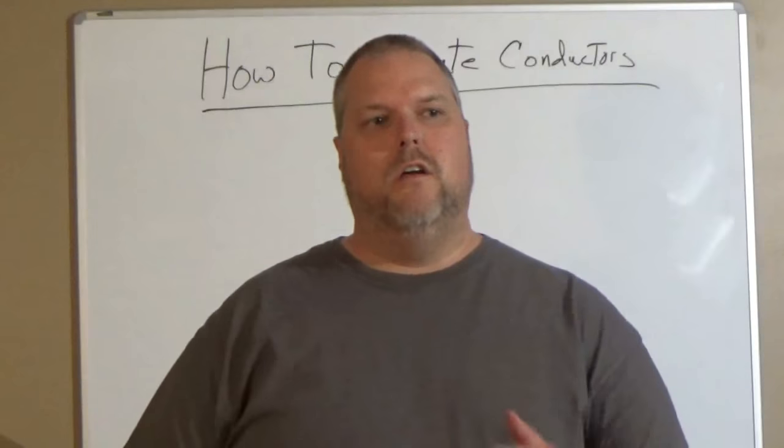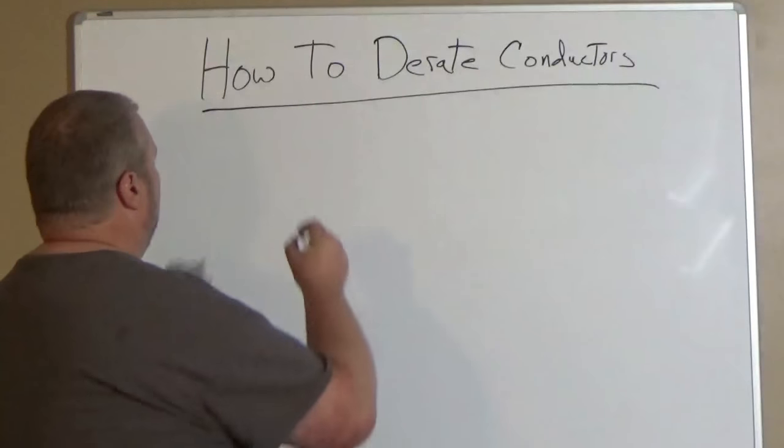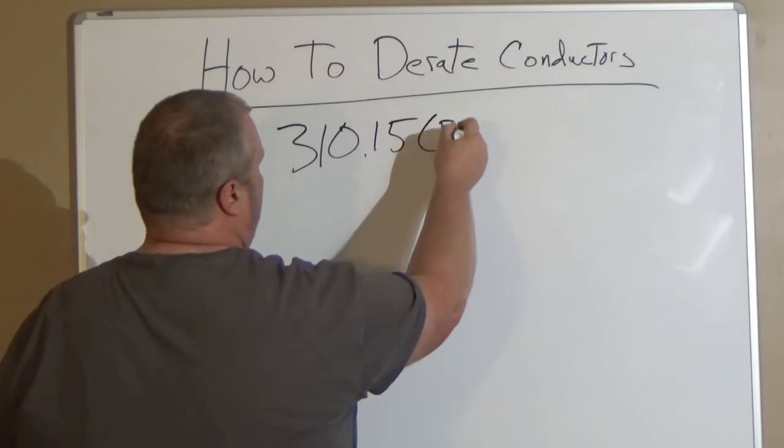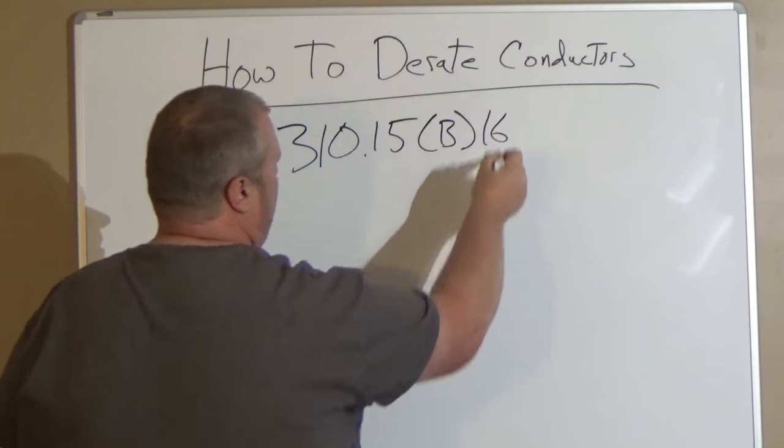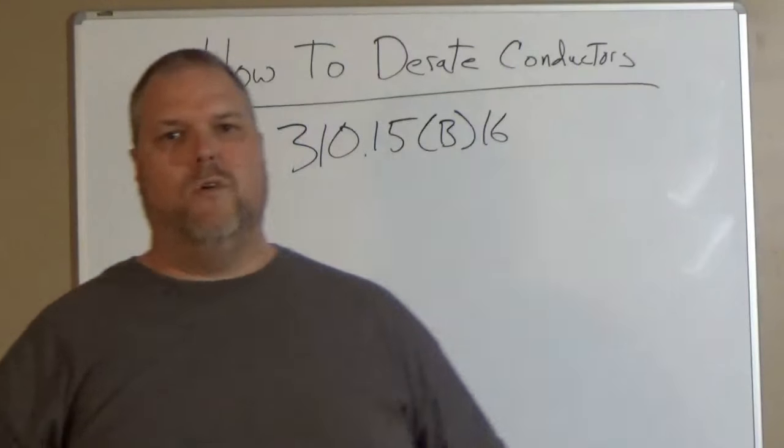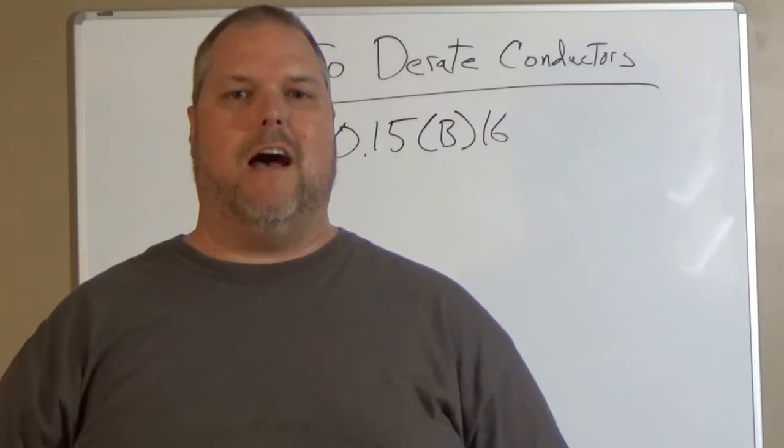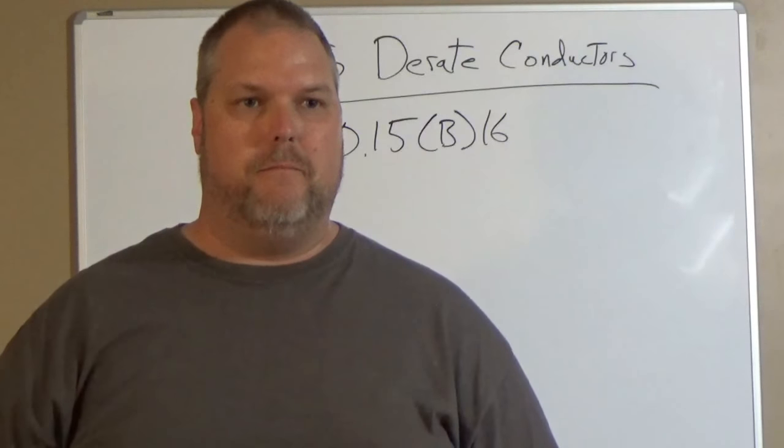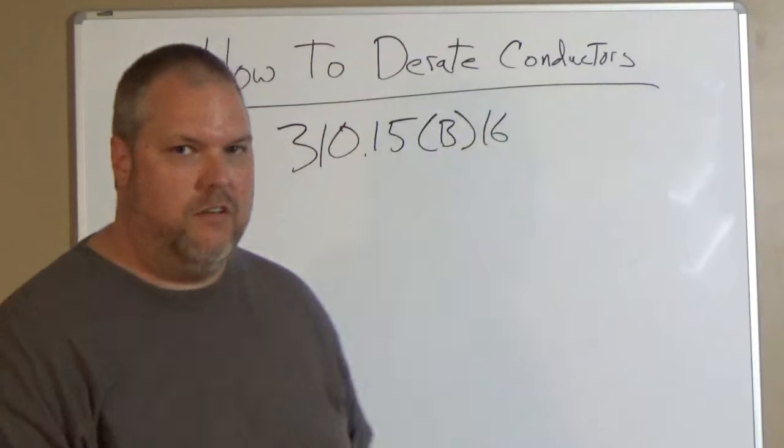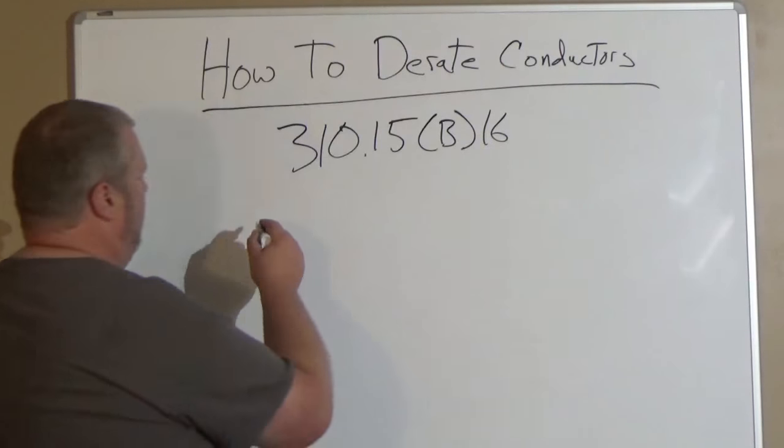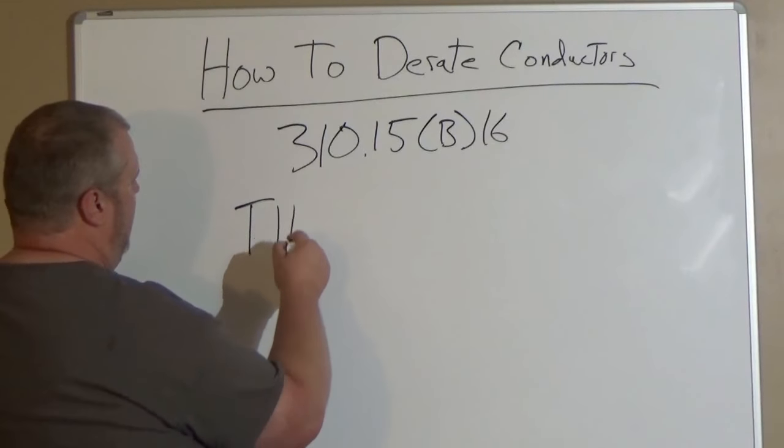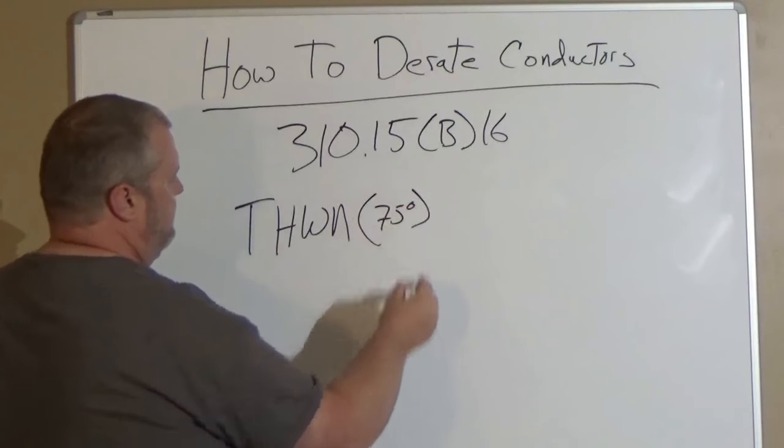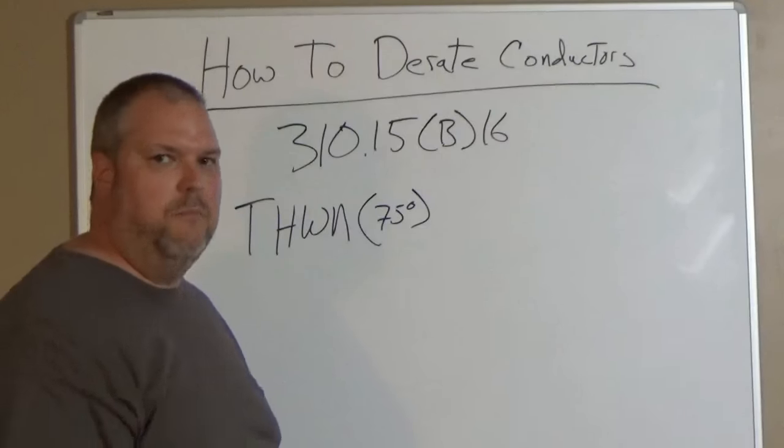So what do we do? We go to 310.15.B.16, and we're going to be looking for a size THWN, which you'll find in the 75-degree column. We're going to look for a number 8. So let's do this, we're going to write on the board: THWN, it's going to be in the 75-degree column, and we're going to size a number 8 conductor.